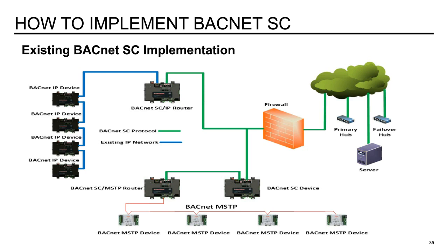Okay, and for the sake of time, since we have definitely run over, I'll make two questions left here. From Patty, if you had an existing install with multi-VLAN, would you recommend multiple SC over IP routers, or is it possible to maintain BBMD on the IP side? I would recommend implementation of SC across the board. If you're going to start, the good news is you can implement BACnet SC in segments. You don't have to do it across the board, but the ultimate goal should be to move directly to a BACnet SC implementation so that you can alleviate the troubles and headaches that go with managing VLANs and those networks.